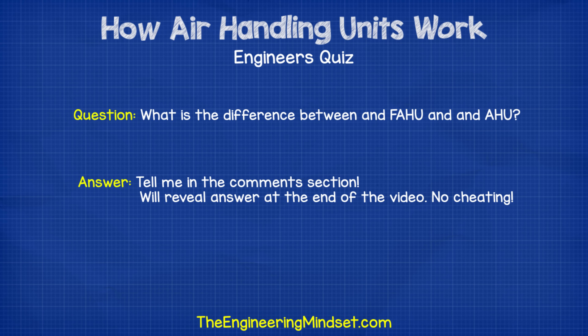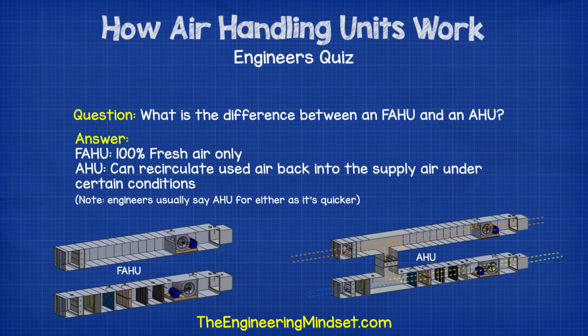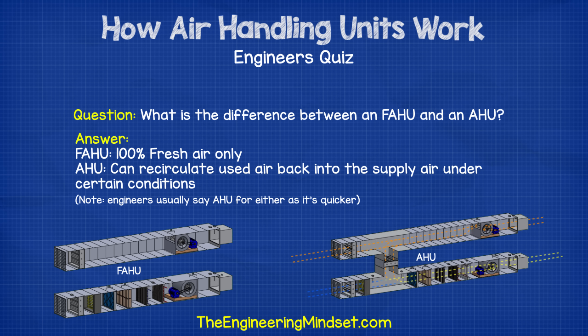The answer to the question I asked at the beginning of the video: what is the difference between an AHU and an FAHU? Simply that FAHU stands for fresh air handling unit, meaning it is an AHU except it can only handle 100% fresh outside air — it does not recirculate any return air back into the supply stream. An AHU on the other hand can recirculate some of its return air into the supply stream. The building application and local regulations will dictate when and if this strategy can be used.